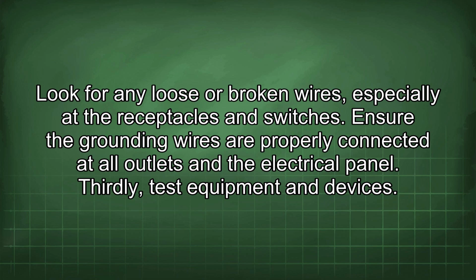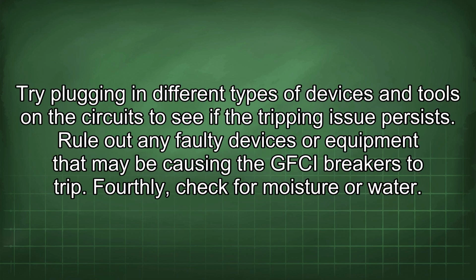Thirdly, test equipment and devices. Try plugging in different types of devices and tools in the circuits to see if the tripping issue persists. Rule out any faulty devices or equipment that may be causing the GFCI breakers to trip.